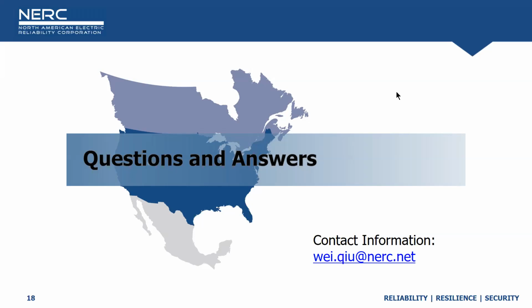So the next question is from Anurag. Network topology problems caused by bad data resulting in SCADA? Yes, good question. I think it will be in SE, because SCADA doesn't need topology. To my best knowledge, SCADA just shows the status, right? They didn't build a topology calculation, and also not all transmission operators have the measurement for the breaker on or off. This is why the state estimator needs to do the topology first before it can do the estimation calculation. I think topology error is more caught at the SE level than SCADA.